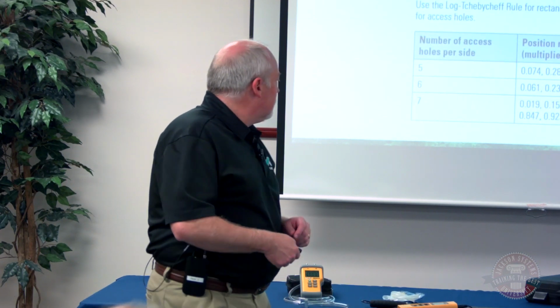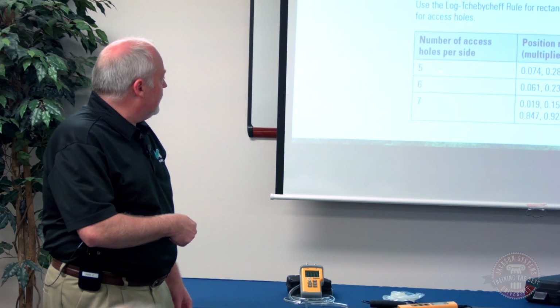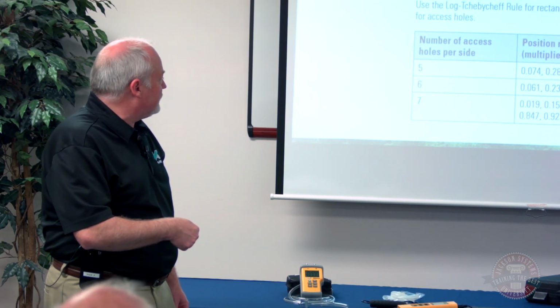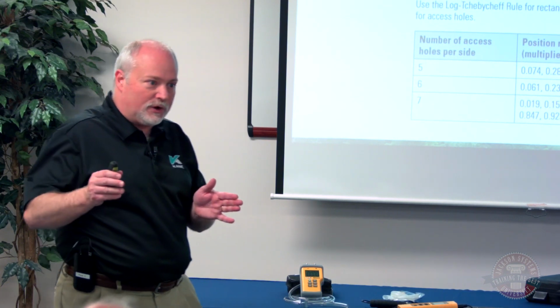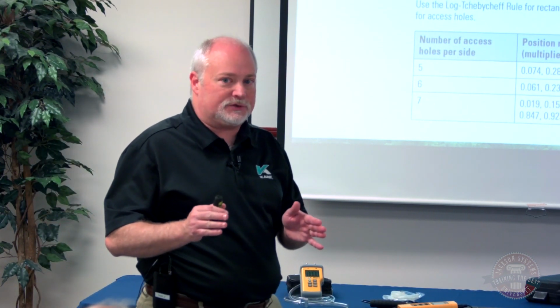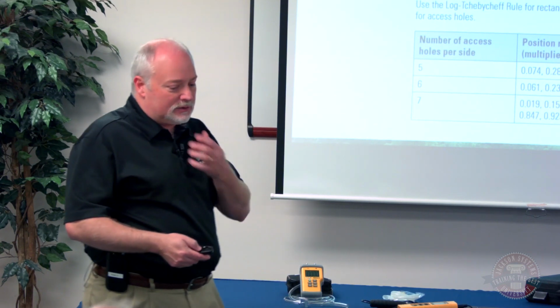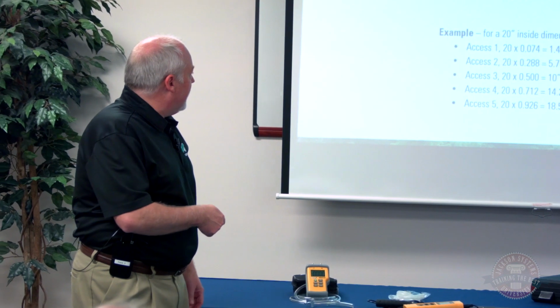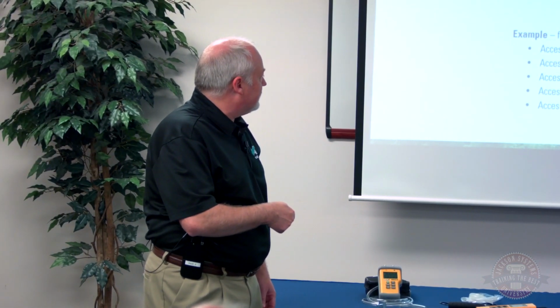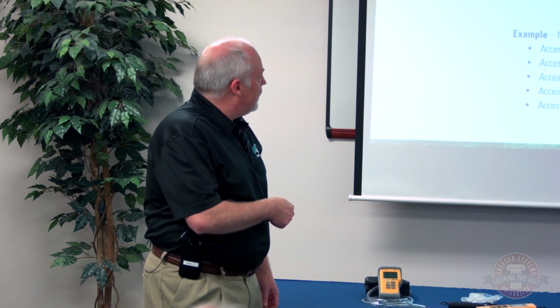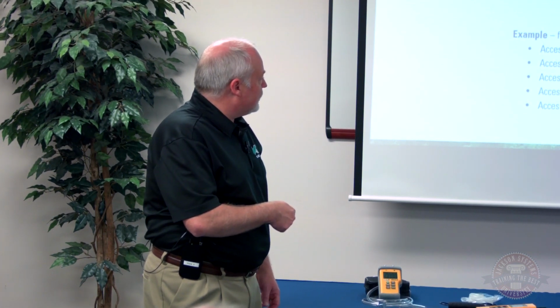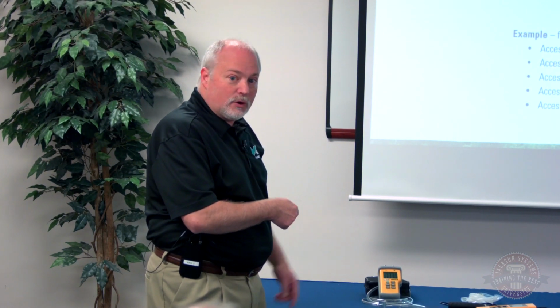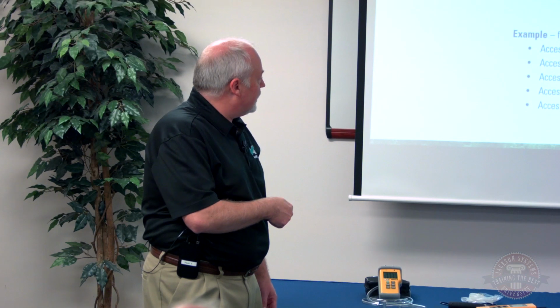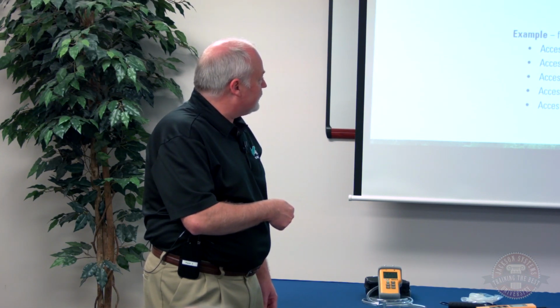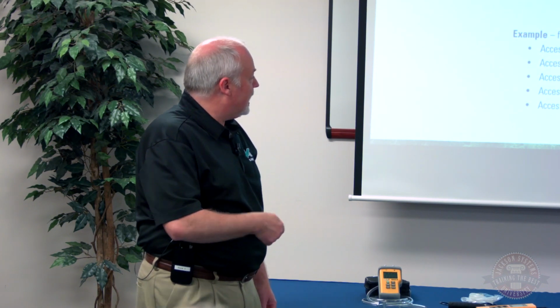Okay. And this gives us our dimensions relative to the inner wall versus the outer wall of making a cross, so we know where to put our holes in our duct so we can get an accurate measurement. So what does that look like? Basically, here's the math. If we were going to use an example of a 20-inch inside diameter opening with 5 access holes, we're going to take the 20 times a 0.074. So our first opening is going to be 1.5 inches over from the wall of the duct. Our second one, 20 times our 0.288, which gives us just about 5 3/4 inches. Then we're going to be over at 10 inches, 14.5, or 14.25, and 18.5.